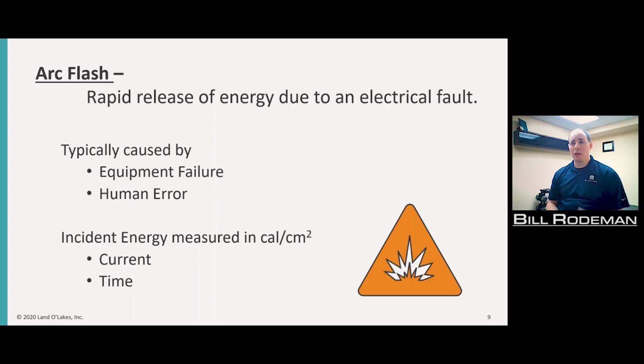The two biggest factors in how much energy is actually released are the amount of fault current available, how much current can hit that piece of equipment, and the time duration, how long the arc flash lasts. If you look at your electrical system, wherever your arc flash is, going upstream to your breaker, fuse, or relay, however long it takes to trip and stop feeding current there, the longer the arc flash lasts, the more energy is expelled during that arc flash.